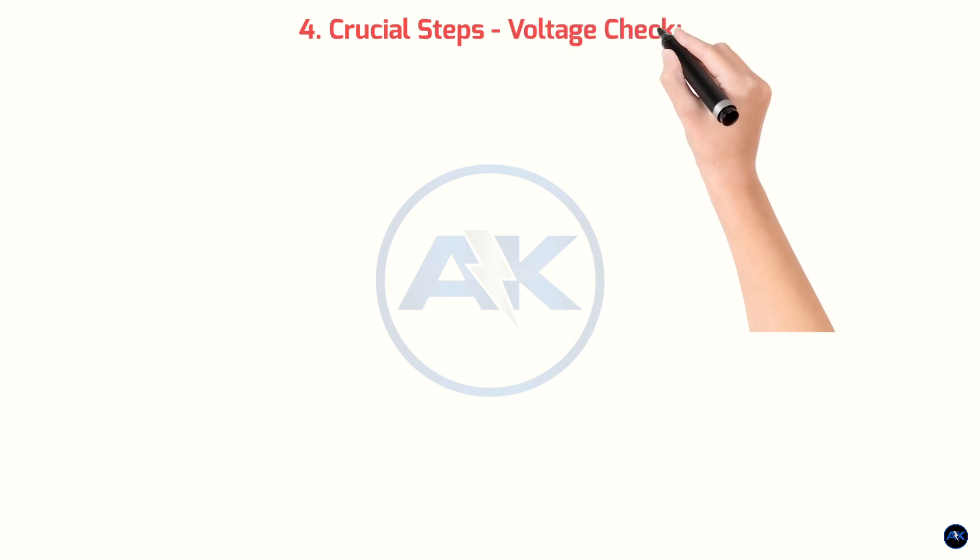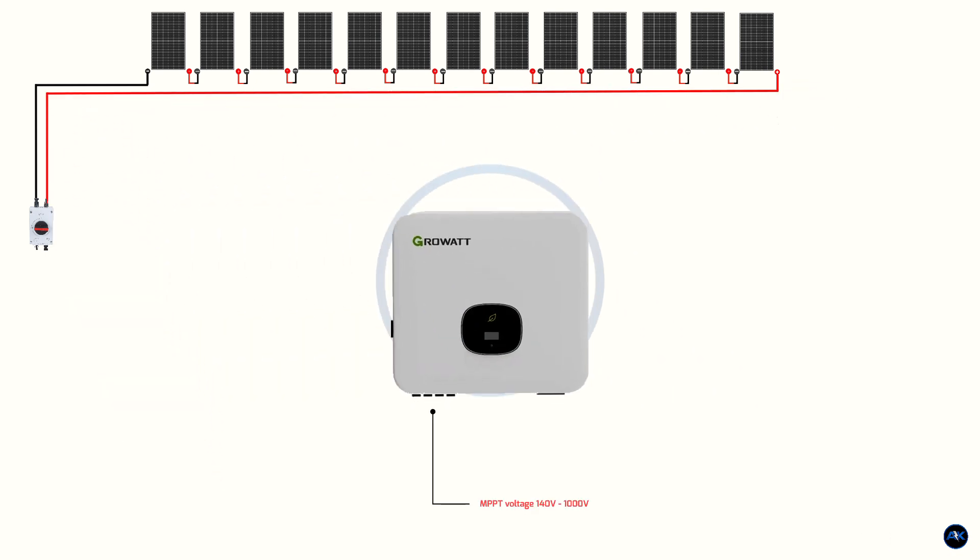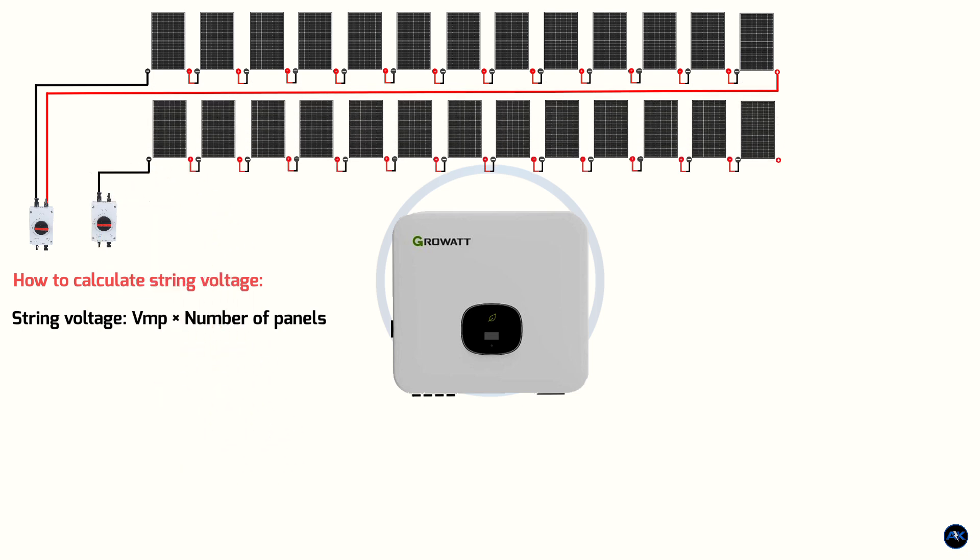Crucial steps. Voltage check: string voltage. You must ensure the voltage of your solar panel string falls within the inverter's MPPT voltage range, 140V to 1000V. How to calculate string voltage? Multiply the panel's VMP by the number of panels in a string. String configuration: you need to decide how many panels you'll have in each string and how many strings you'll have. This depends on the panel's voltage and the inverter's MPPT trackers. Example: you could have two strings of 13 panels each, total 26 panels or other configurations. Ensure the voltage of your solar panel strings is compatible with the inverter.